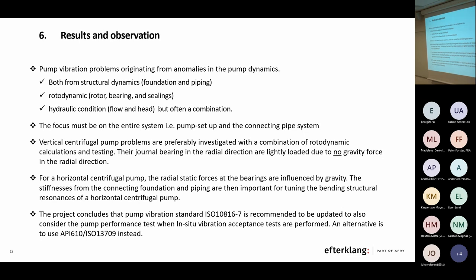So then put it in a more structured way to see, okay, what can it be? What kind of physics do we have here for the pump? Is it a vertical or a horizontal? Okay, think about the rotor shaft, the radial offset. What can be the problem here? Some sealings, some clearances are not working okay. Is it a horizontal centrifugal pump? Okay, think in the first place, is it a bending resonance? Then think foundation and pump connecting pipe system, etc.